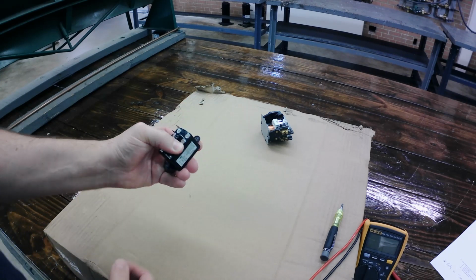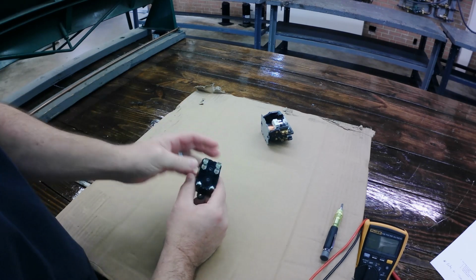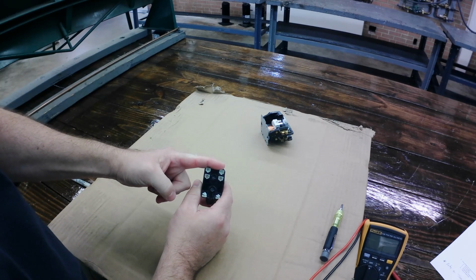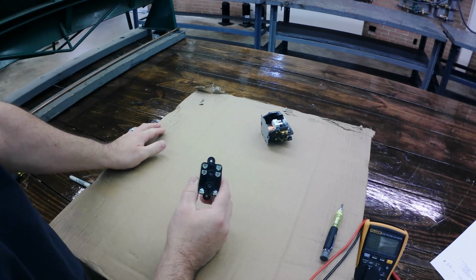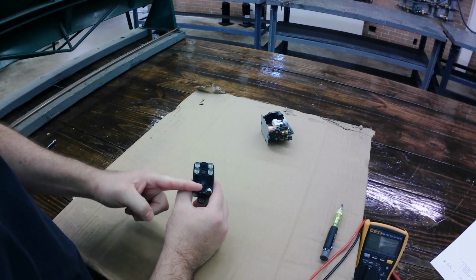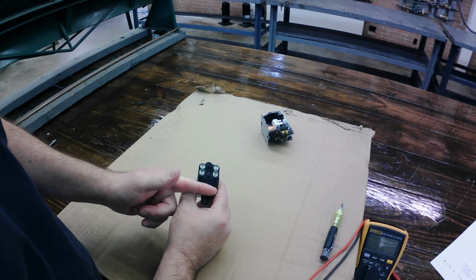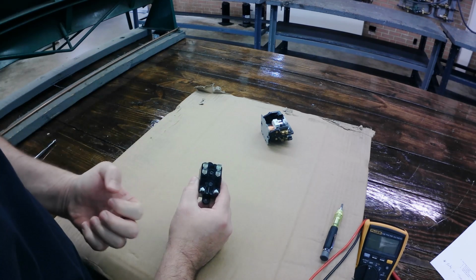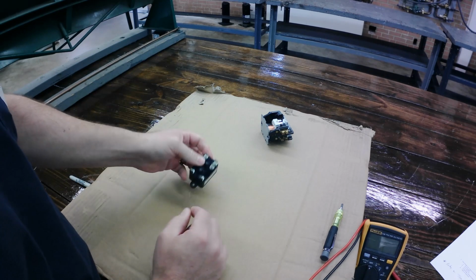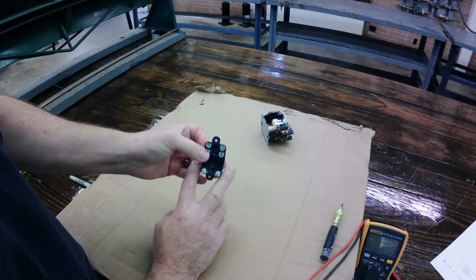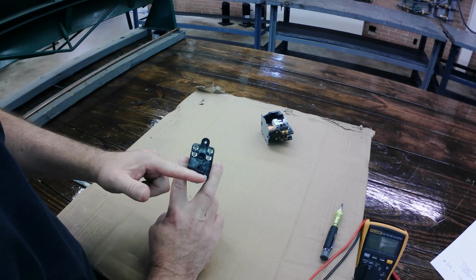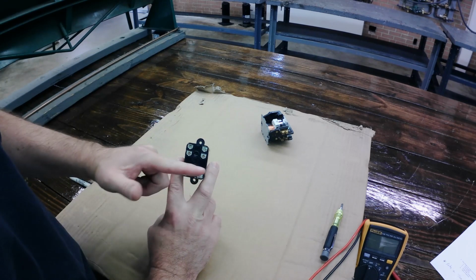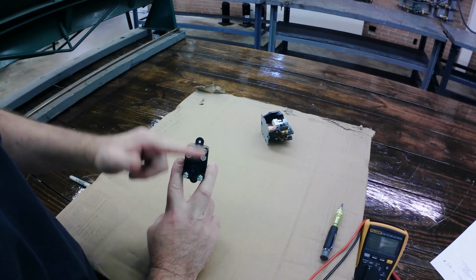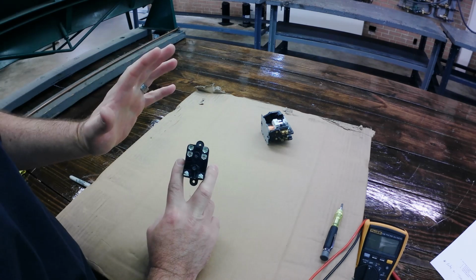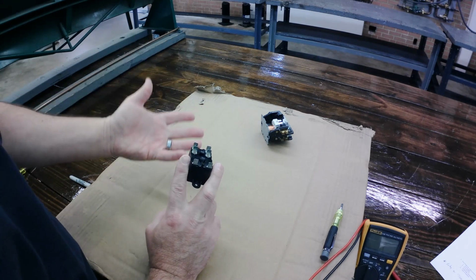All right, so the switch is a switch. Switches are in line with one leg of power. Coils, they are a load, so they're going to see both sides of power. But you have to remember that the load is different than that switch. I can check these individually, the low voltage coil and then the high voltage switches. We can do those individually and still troubleshoot properly.